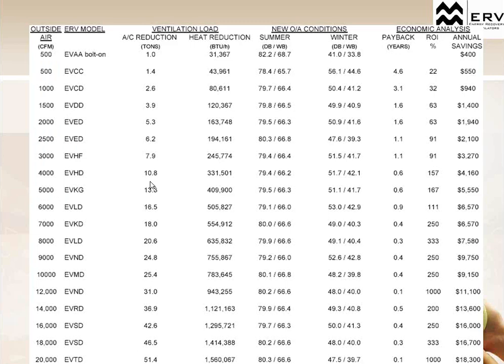We could reduce the cooling tonnage requirement of the HVAC system by approximately 13 tons. So anywhere where you have 5,000 CFM of outside air, you can actually reduce that cooling requirement on the HVAC system. So that's going to save you energy and money up front if you're replacing that system. And that's not the only real story.